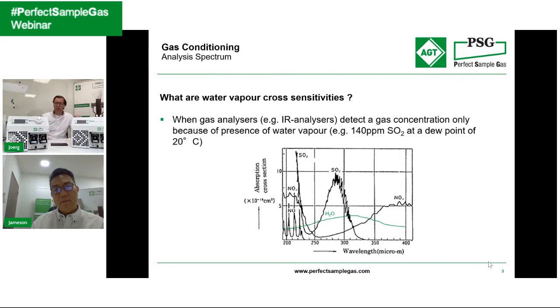Because, and this is something we will also discuss, the gas dryer, the gas cooler, will change the gas sample. So if all other components like the probe and the heated sample line have the task of not touching or changing the gas sample, it is the task of the gas cooler to remove the water, and by removing this water, this is really a crucial process.